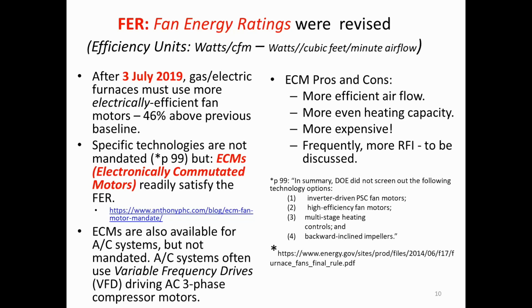I have one in my furnace. It's more efficient airflow, more even heating capacity. The speed is adjustable from high to low. You can adjust the torque and the frequency. However, frequently there's more RFI, and that is now our problem.